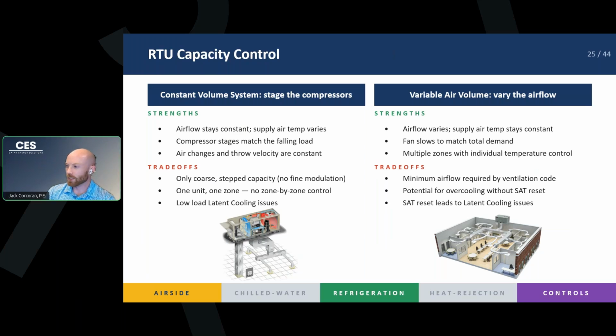You're going to overcool, turn it off, then it'll drift back up, turn it on, overcool, turn it off. So that maybe is not what you want in your space. But that's one way to do it. It's very simple. Another trade-off actually is that this is best for single zones, right? If you had different areas of the floor that needed a different amount of cooling or heating, this is only going to be able to send one temperature throughout the whole system. So every zone that it sends it to is going to be the same temperature, right? You can't have one room be hot and one room be cold. You're going to be stuck with what you got. So that's why it's better for large open areas, not zone by zone control.